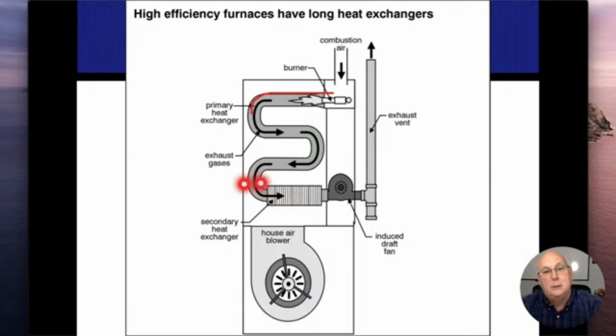Now, all the condensation that's going to be created in here, because these are condensing furnaces, so they are going to be creating water or condensation, that's going to settle down here. And if it can't drain out, it's going to be very corrosive. I forget if it's alkaline or acidic, nor does it really matter. It's going to start corroding the heat exchanger, and then we're going to start getting drips coming down to the floor. Look on the floor when these things are running, see if it's wet.